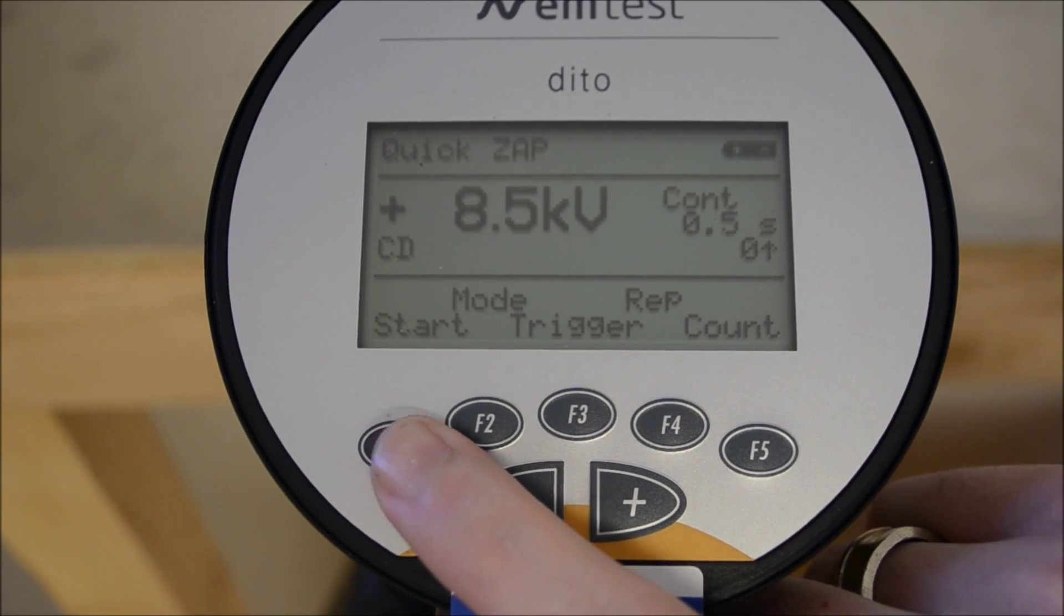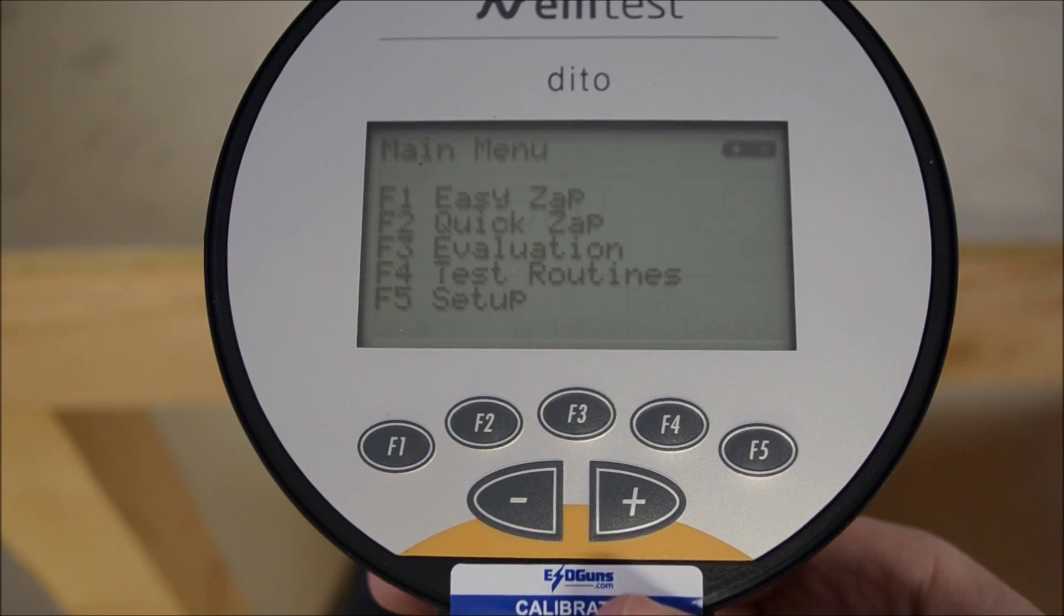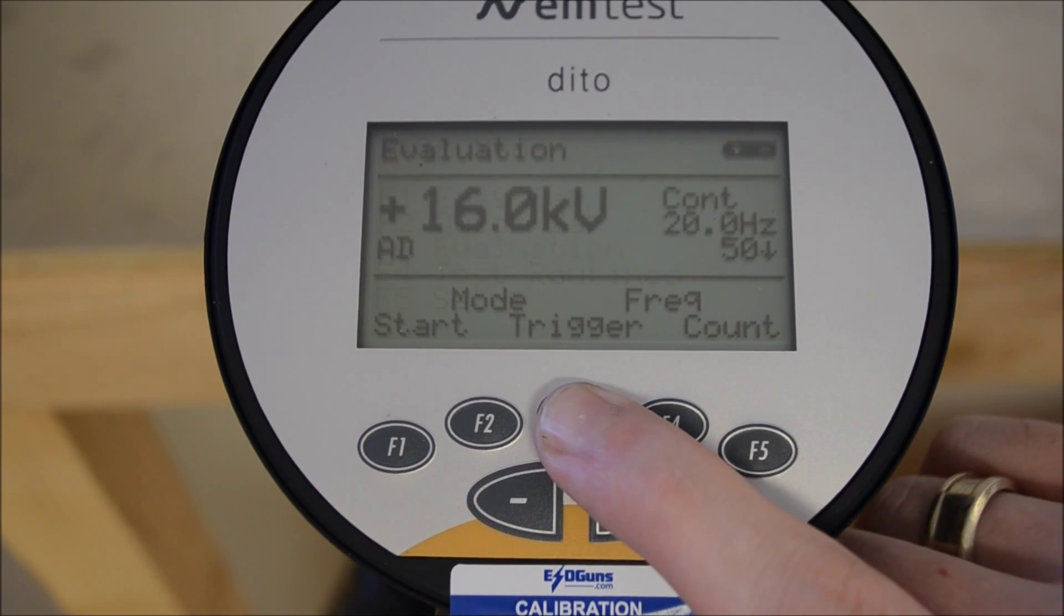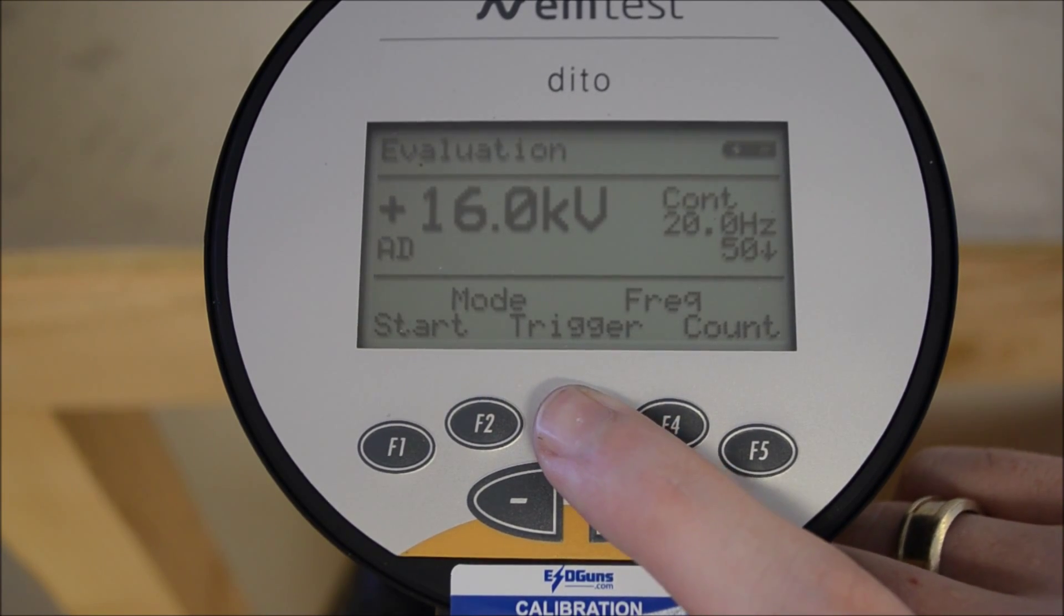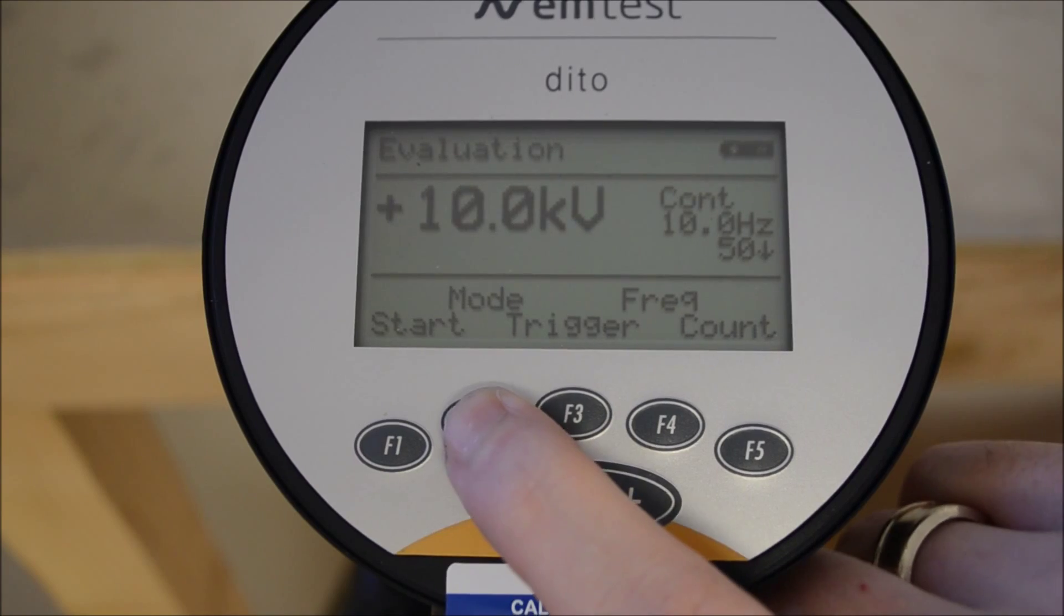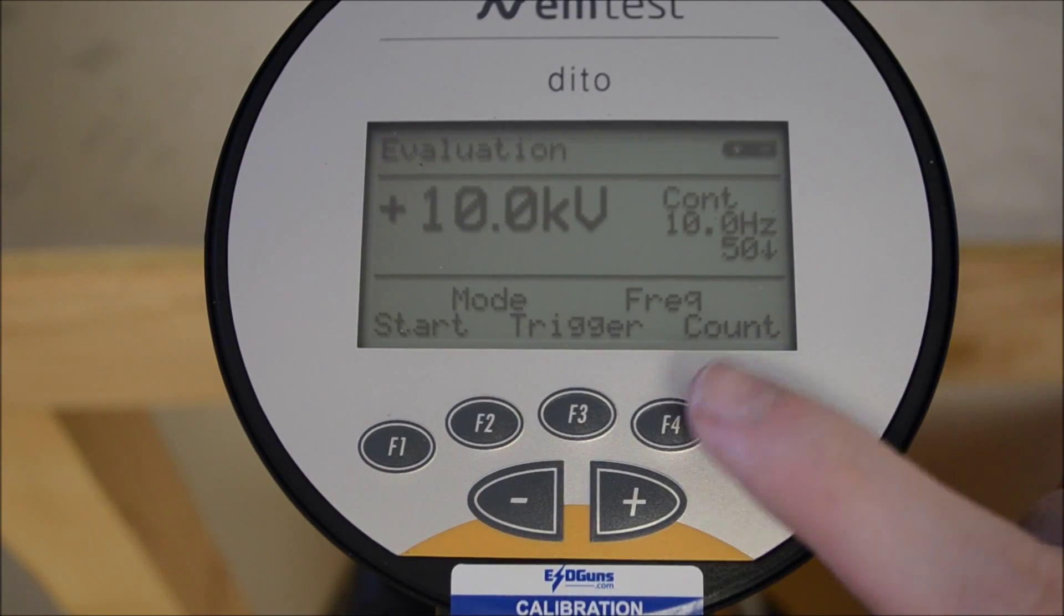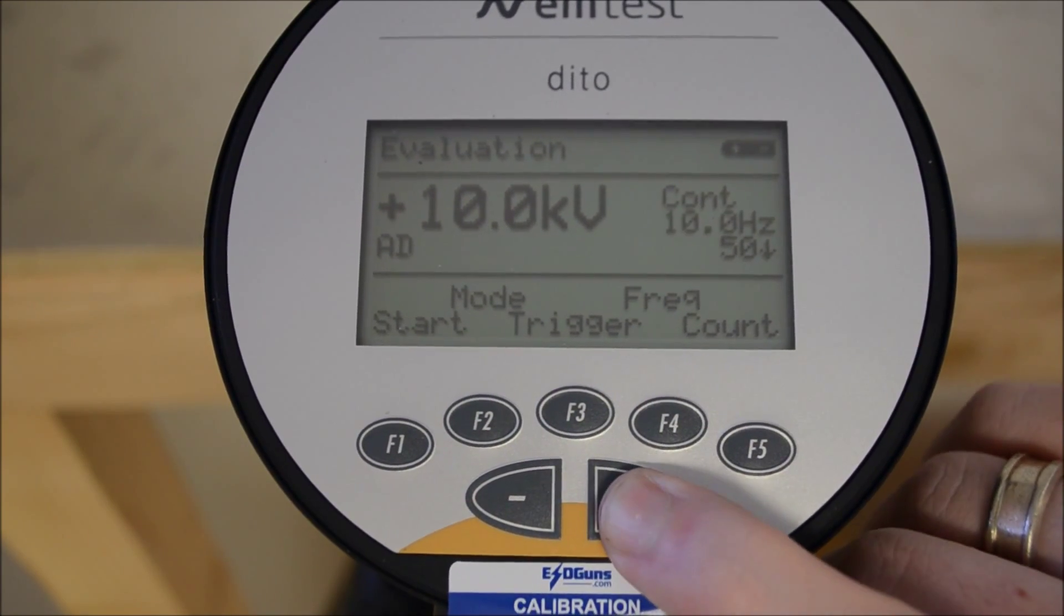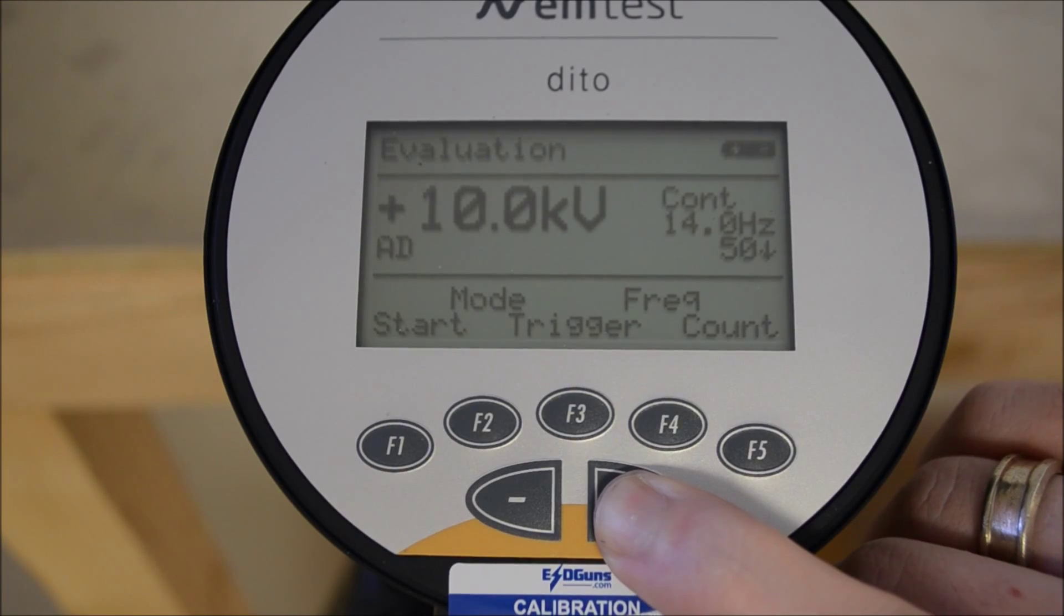Allowing us to use the trigger to back out to the main menu and move into evaluation mode. Evaluation mode can be used to check the DUT for sensitive test points. The preferred method to find these points are in air discharge mode. In this section we can speed up the discharge frequency to 20 Hz.